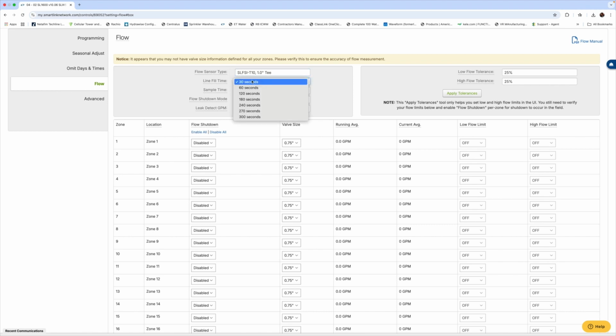Our line fill time is going to refer to the amount of time it takes to get the air out of the zone furthest from the point of connection. So in this example, I'm just going to say that that zone takes 2 minutes. So I will set my line fill time to 120 seconds. And that's going to be important to capture a good resolution as the flow is running through that paddle in your insert. So that's going to be really important to find out, how long your line fill time is so that you're not trying to capture information too early. I'm going to go ahead and leave the sample time at 60 seconds. I just feel like I get a really good resolution with that time frame.